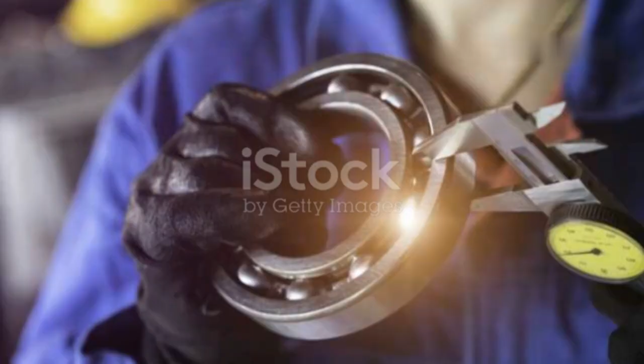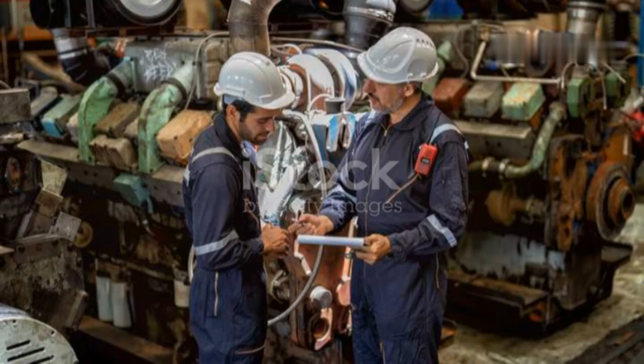Once the measurement system is deemed acceptable, ongoing monitoring is essential to ensure that it continues to perform as expected. This involves regularly checking the calibration of the instrument and conducting periodic gauge R&R studies. By following these steps, organizations can implement a robust MSA program that ensures the accuracy and precision of their measurements, providing a solid foundation for quality control and process improvement initiatives.